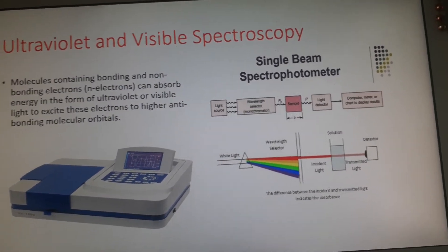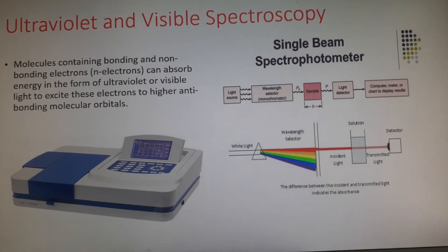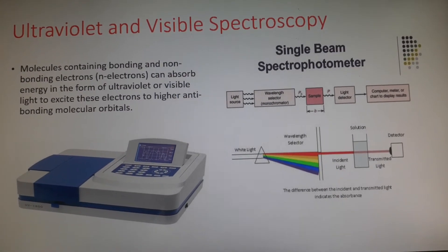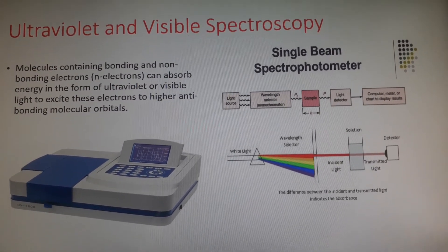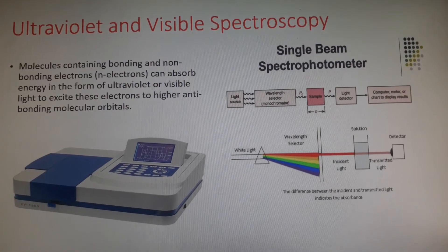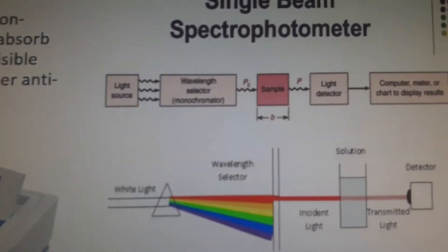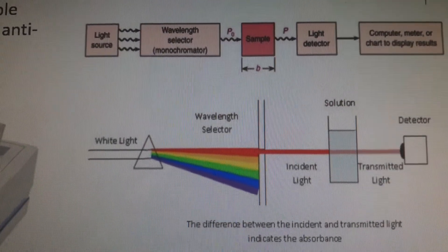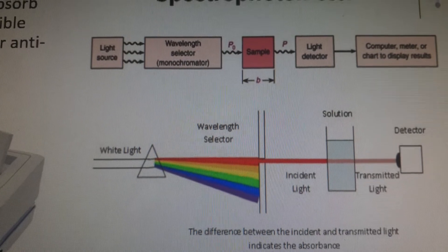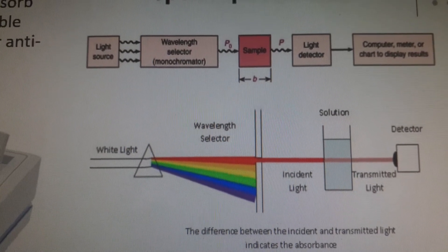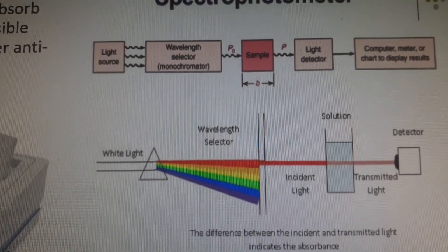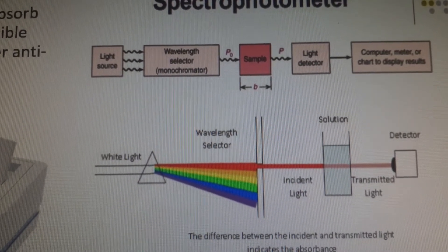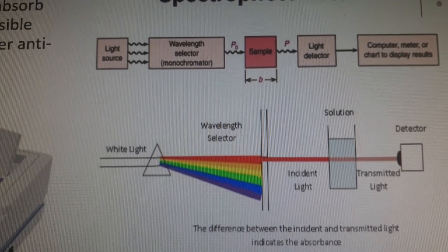In UV-visible spectroscopy we have two forms: one is called a single beam spectrophotometer and the other is called a double beam spectrophotometer. In the single beam spectrophotometer, as seen in the diagram, we have the light source, then the selected wavelength passes through a monochromator which acts as a filter, and the desired wavelength passes through. The light then passes through the sample, and the absorbance depends on the concentration as per Beer-Lambert's law.